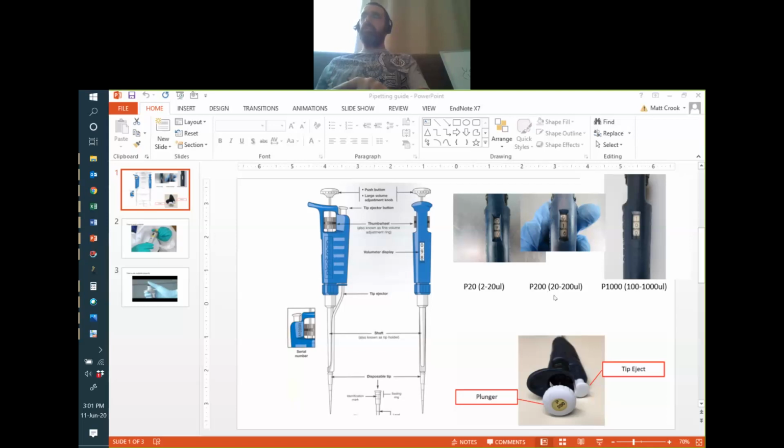So the middle one, the rule of thumb, and this is interesting because I learned this from watching one of these videos. I'd already known it, but the easiest way to describe it is, for the middle one, you've got 3 digits: hundreds, tens, and singles, because the largest you can do is 200, since it's a P200.